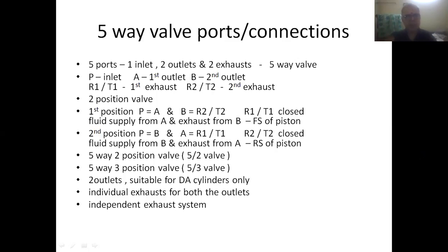And finally, this valve is provided with two outlets, so it is suitable for controlling double acting cylinders. And separate exhausts are provided for both the outlets of the valve, so therefore it is referred to as an independent exhaust system.